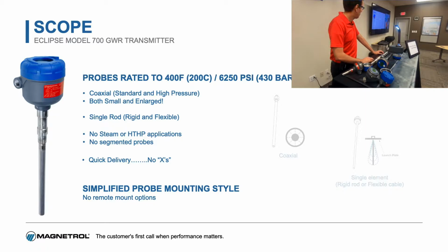Also, we're going to limit the permutations up to 400 degrees Fahrenheit and up to 6250 PSI. So you don't have any of the exotic high pressure, high temperature steam probes and gas application probes listed. 400 degrees Fahrenheit, just to put it as a reference, a 250-pound boiler, like a Cleaver Brooks boiler, for example, can go up to 250 pounds, which translates to about 406 degrees Fahrenheit. So anything from package boilers, deaerators, any of your very, very common applications, the 700 is ideally suited for that. So as I mentioned, there are no steam or high temperature, high pressure application probes, or segmented probes. There were going to be no specials.